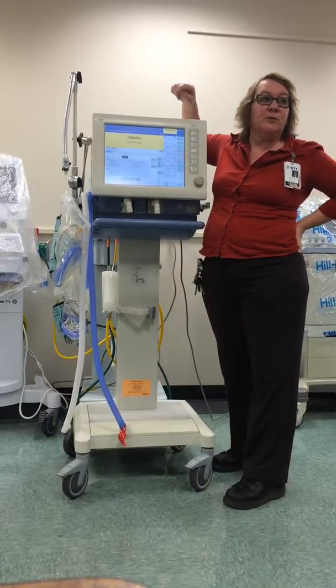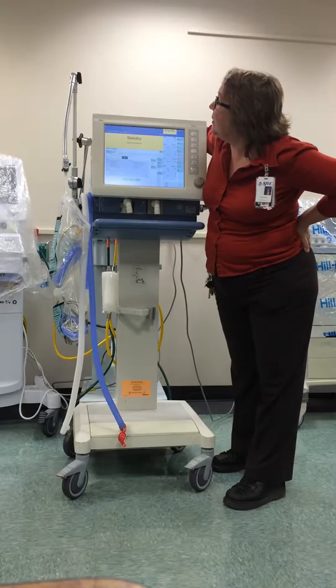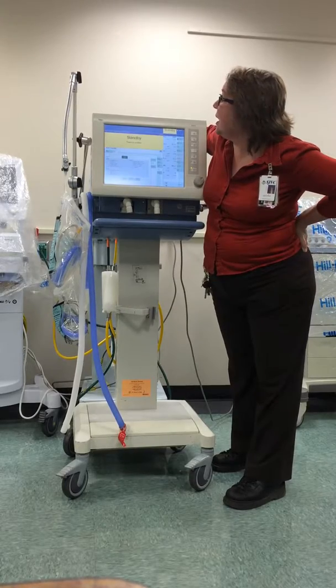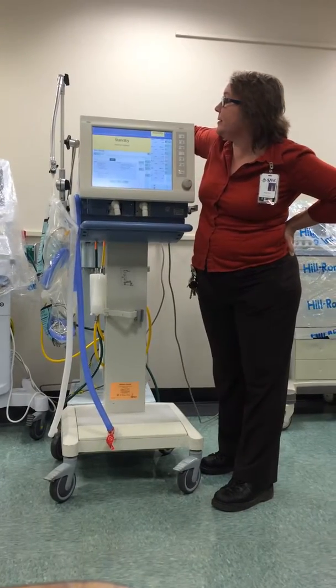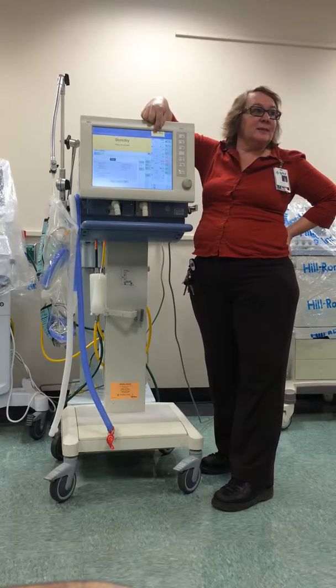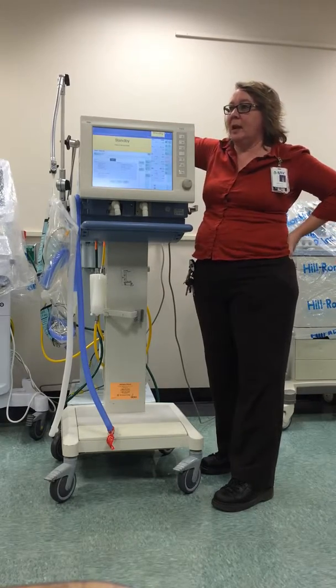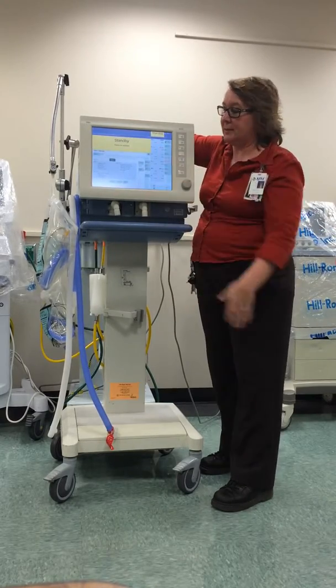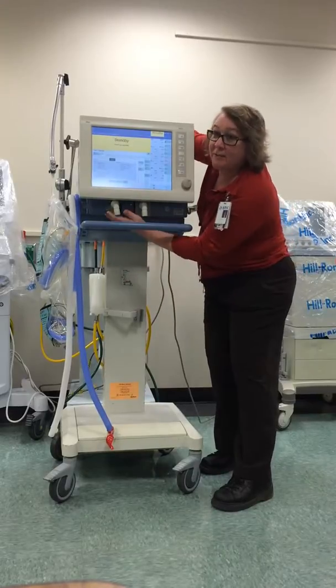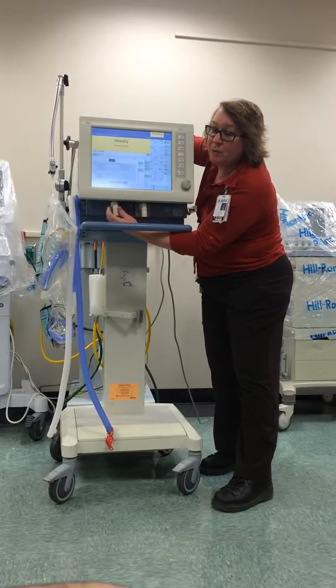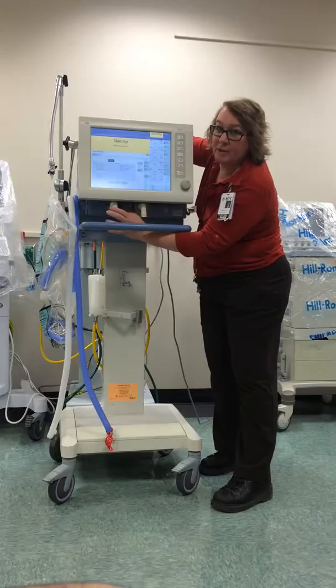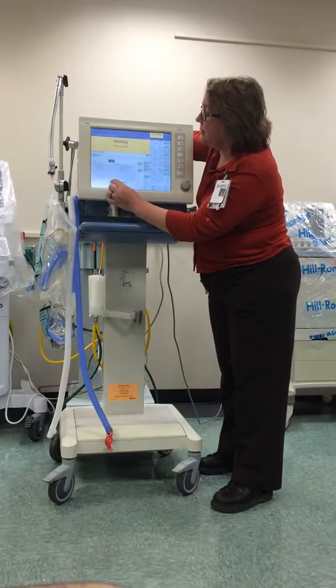And I'm going to tell you a few things as we go along. Up here at the top, the first thing it says is check correct position of the exhalation valve, and you see a timer. It's 60 seconds. You can do it in plenty of time, but it's telling you to do it within 60 seconds. The exhalation valve is down here, which I'll pull out and show you when we're done with the calibration. It's going to be in the correct position. Hit yes.